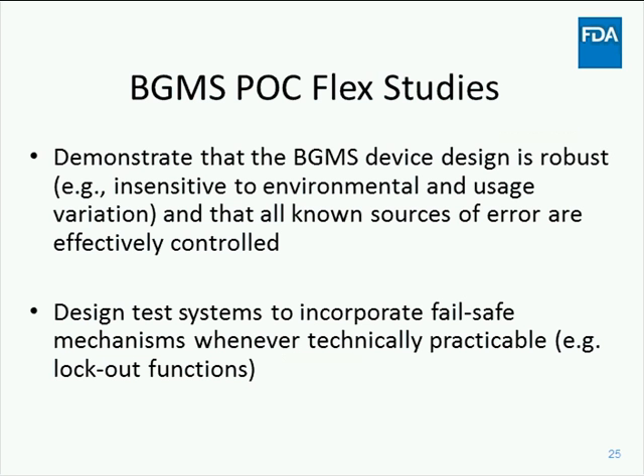The BGMS guidance also includes a description of flex studies that should be performed, some of which are new from what we can currently see. These studies are designed to demonstrate that the BGMS device design is robust and that all known sources of error are effectively controlled. The test system design should incorporate fail-safe mechanisms whenever it is technically feasible. Examples of fail-safe mechanisms are the use of lockout functions to ensure that the test system provides no result or an error, rather than displaying an incorrect result in cases where, for example, test conditions are inappropriate.